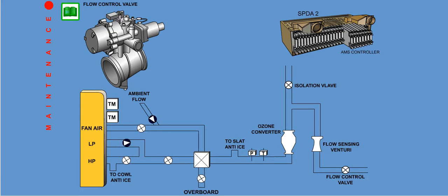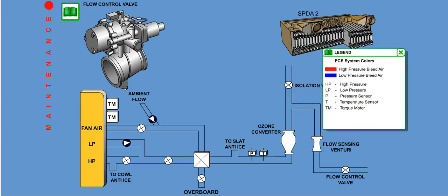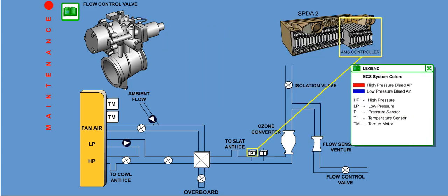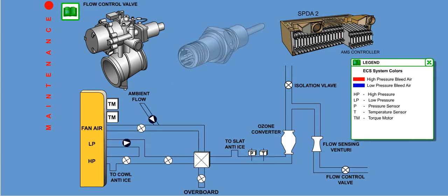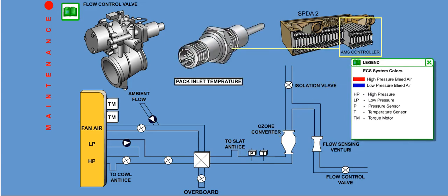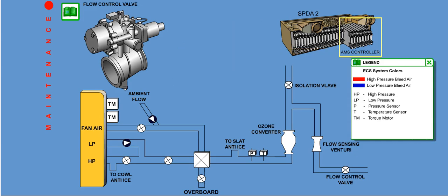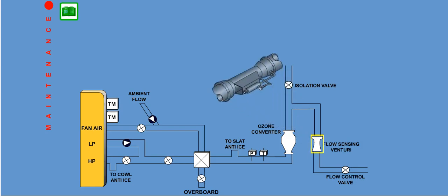The valve operates as follows. The flow-sensing Venturi differential pressure signal is sent to the AMS controller for calculation. For internal calculation, the AMS also uses the manifold bleed pressure and the pack inlet temperature to determine airflow to the packs. The controller millivolt signal is sent to the flow control valve to define the valve position that will modulate the airflow. The flow-sensing Venturi is a steel duct.